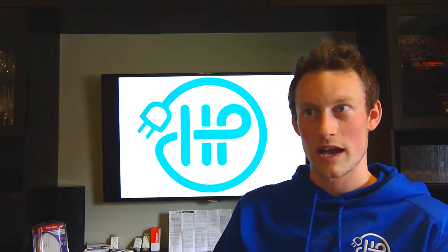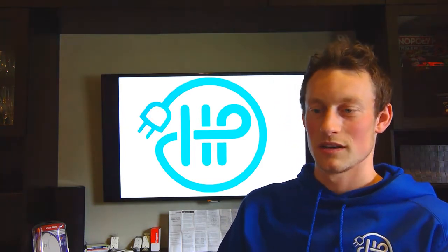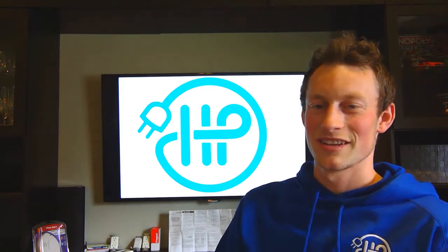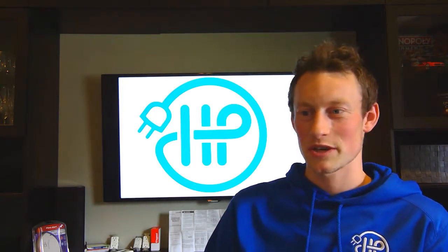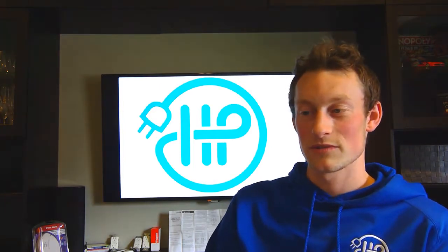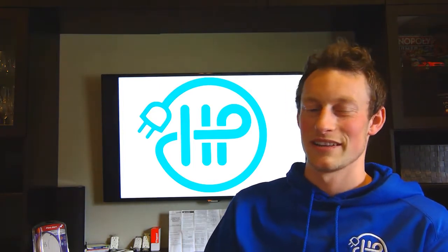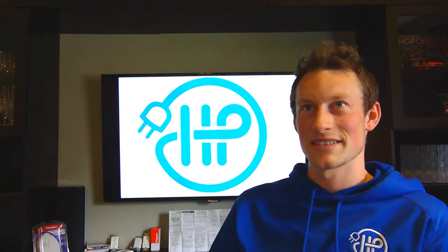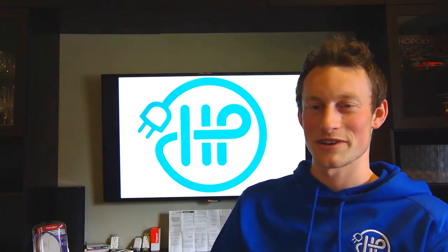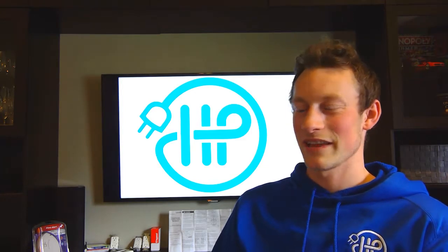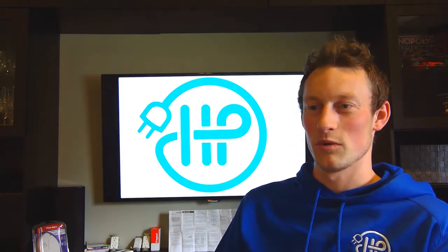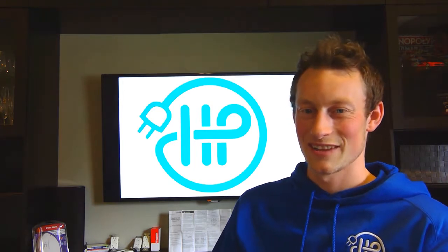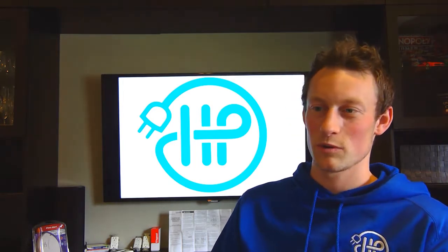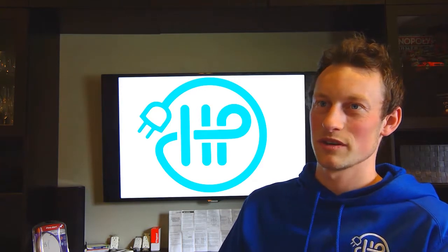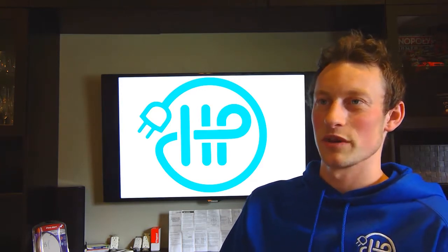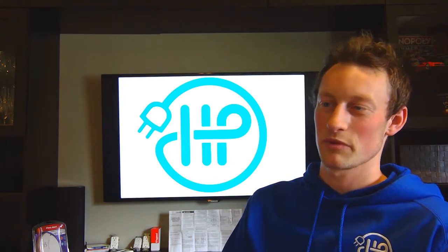Many devices will have arcing on a regular basis. What devices should be arcing? Well, drills will arc. Squirrel cage induction motors will arc. Sometimes your sump pump should arc. It's a motor, and that's what it will do. The devices have come a long way from when they first started out. When they first started out, any light switch that was maybe a year old would arc and trip the breaker. A lot of LED lights were not compatible with arc faults. A lot of situations would provide a tripping situation in the case of having an arc fault breaker.